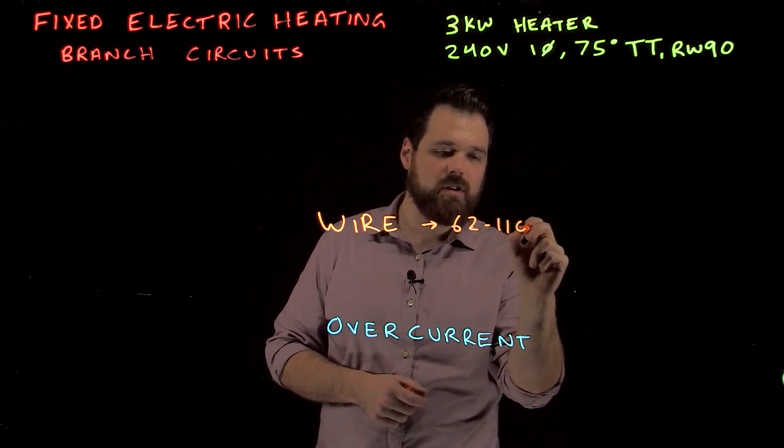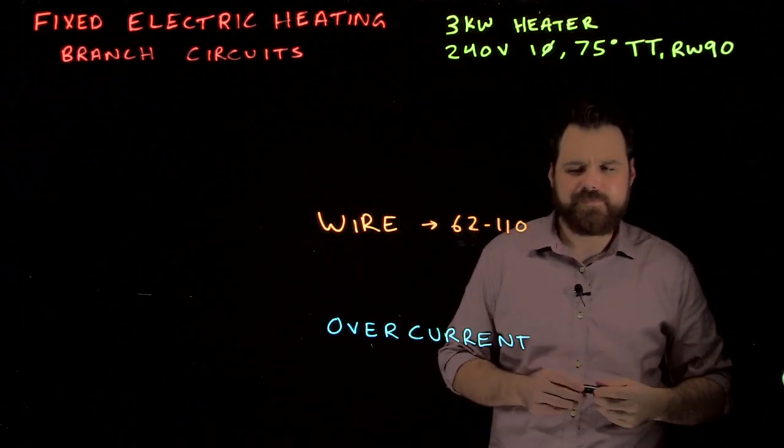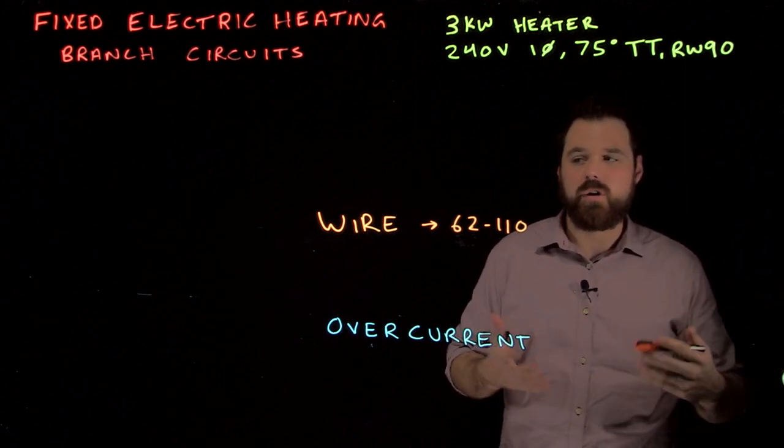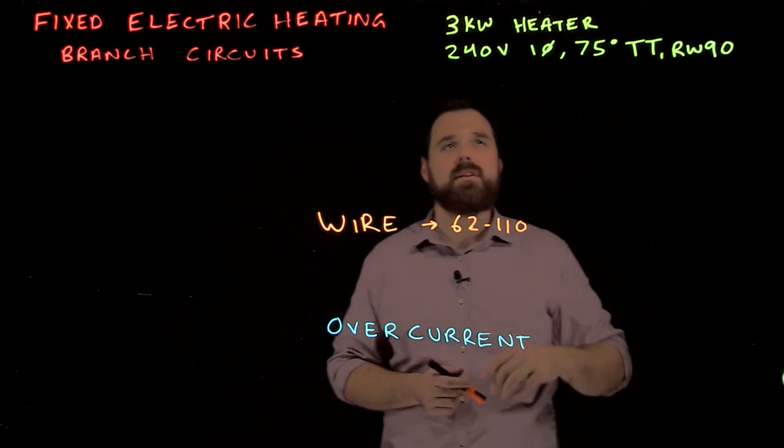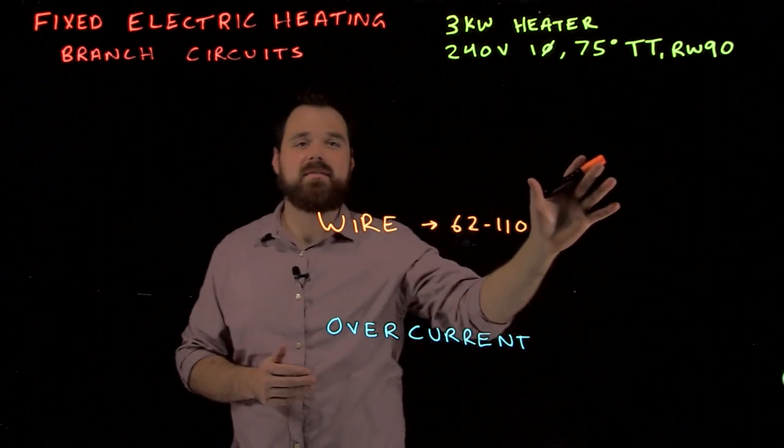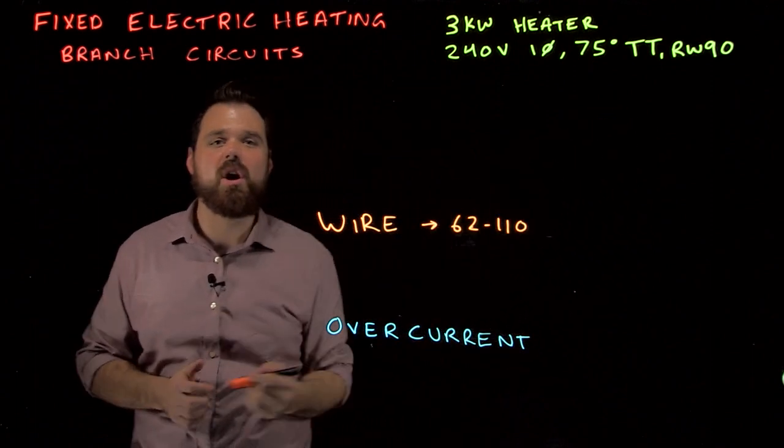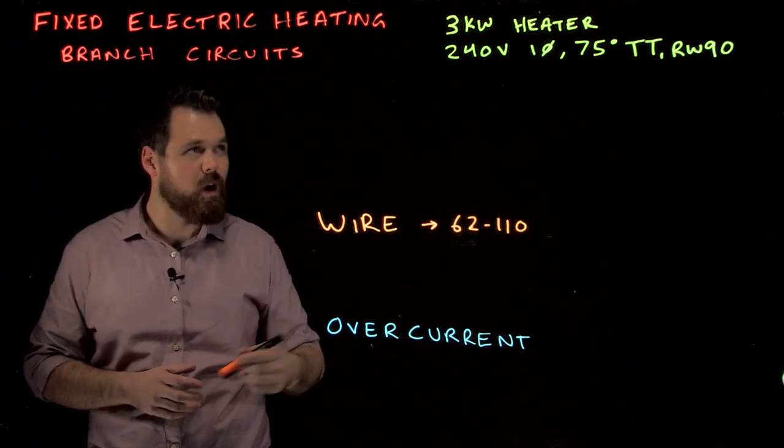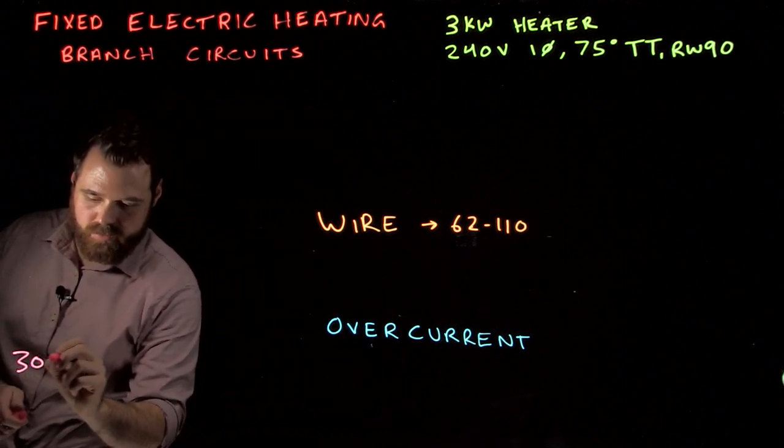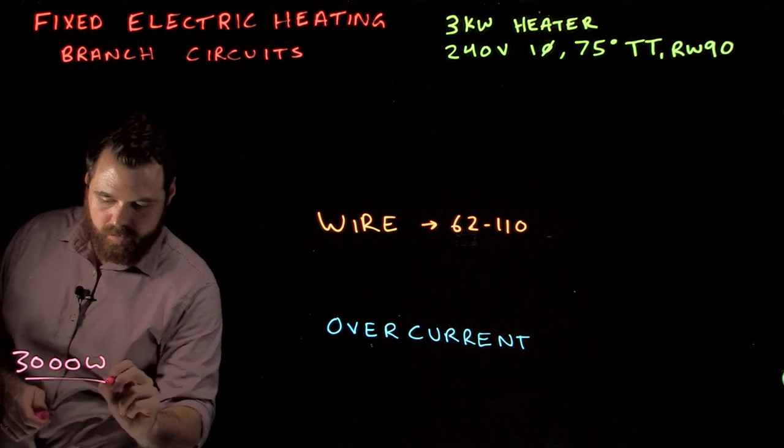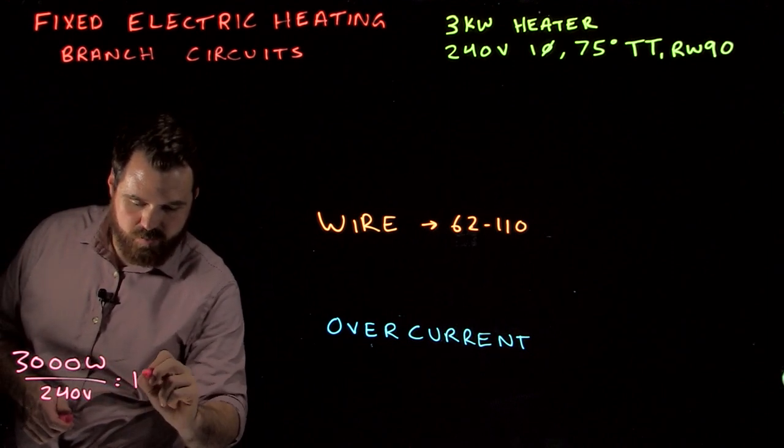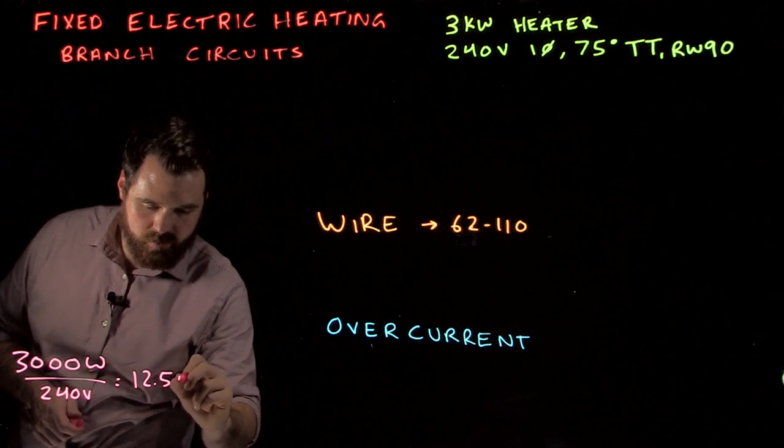62-110 talks about conductors. It basically tells us conductors need to be able to handle the load. So in this case we are dealing with a 3 kilowatt heater, 240 volts single phase with a 75 degree termination temperature using RW90 wire. Well, in this case for our load we are going to go 3,000 watts divided by 240 volts which is going to give us 12.5 amps.